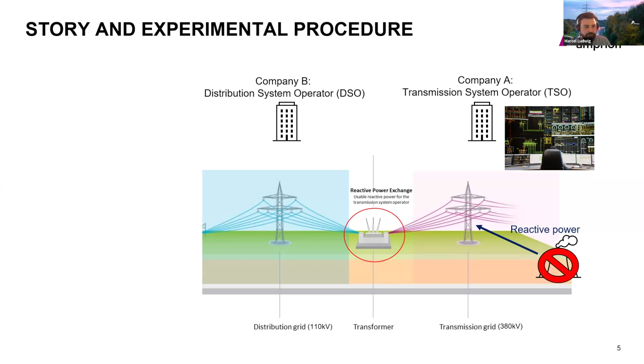Sources for reactive power, and therefore we make a request to the distribution system operator, because we have a huge expansion of wind power plants in the distribution grids, and there new grid customers are situated. So what we do: we make a request of reactive power to the distribution system operator, and the distribution system operator makes a request for adjustment of the operation point to the wind power plants.